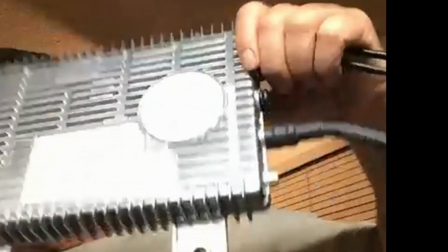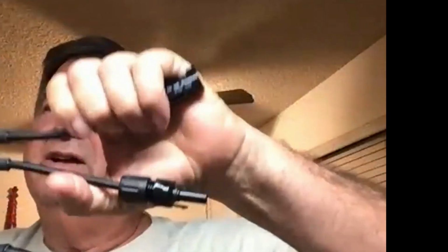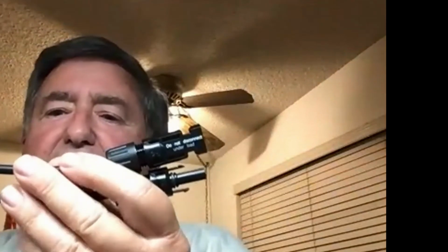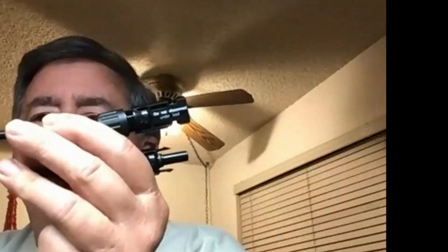If you look at this unit again, it's pretty well encased. What's not encased are the wires coming out of it. These DC wires, to get 300 watts at say 32 volts, you're going to be near 8 or 9 amps feeding this. So if you couple long wires onto this thing, depending on the internal filtering of the unit, you could generate some AC hash and some RF. The longer the wires and the sloppier the installation, the greater the chance that's going to happen. There's a best way to filter that stuff out.